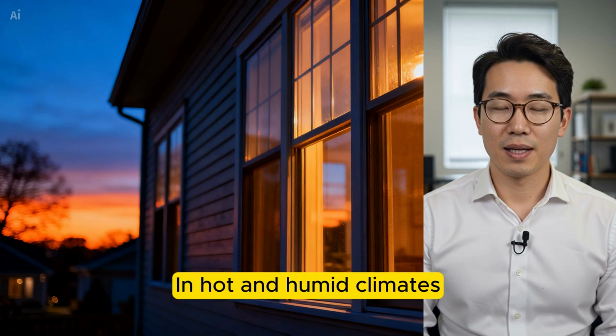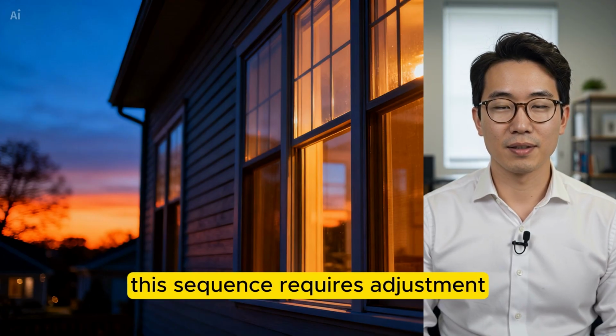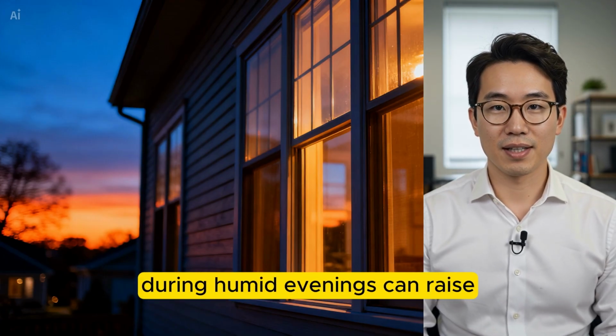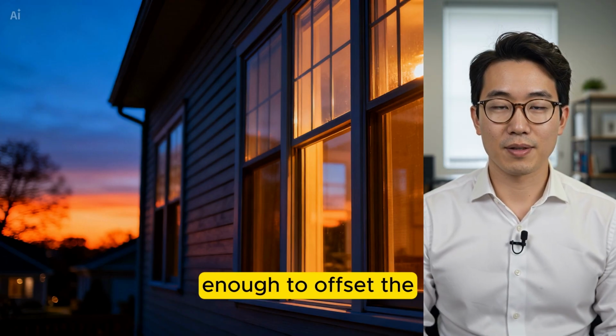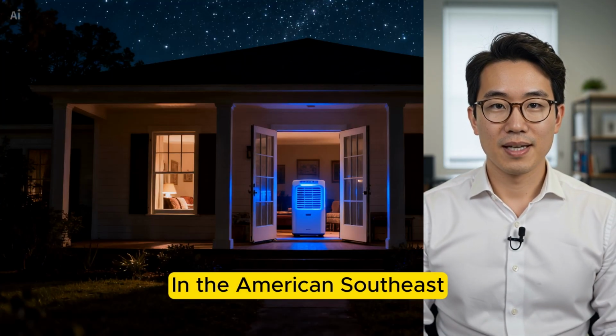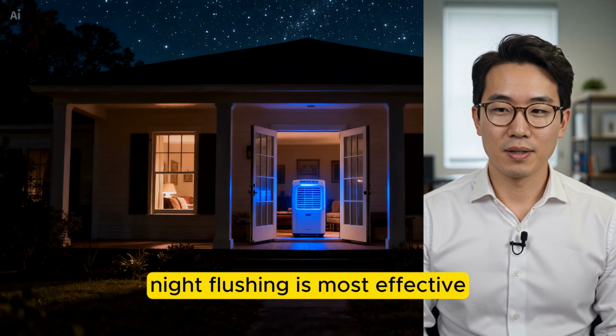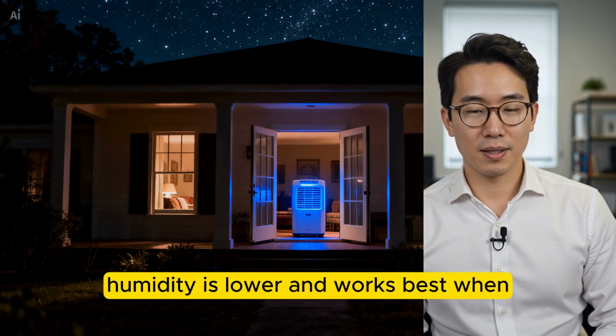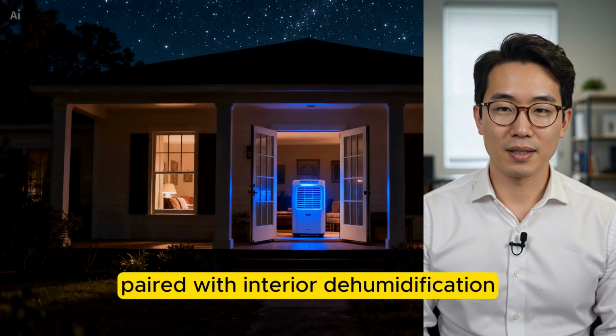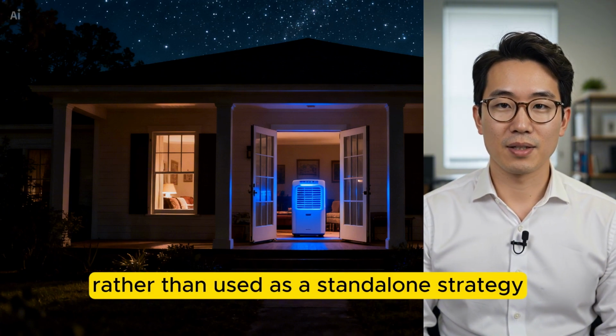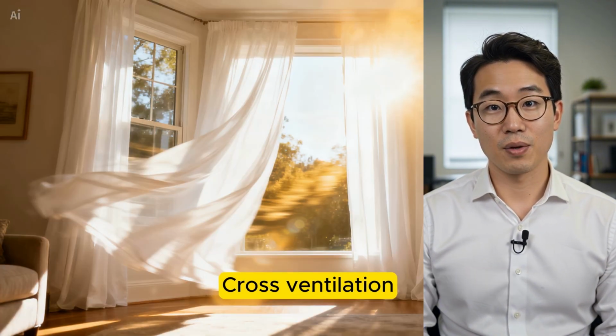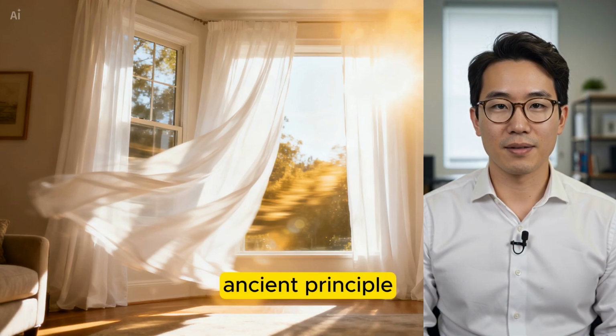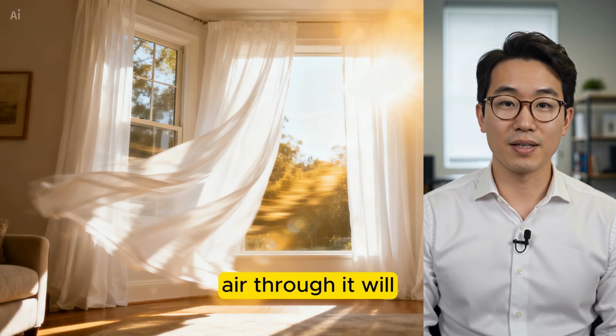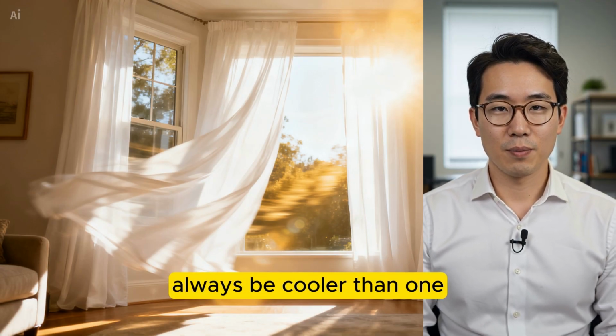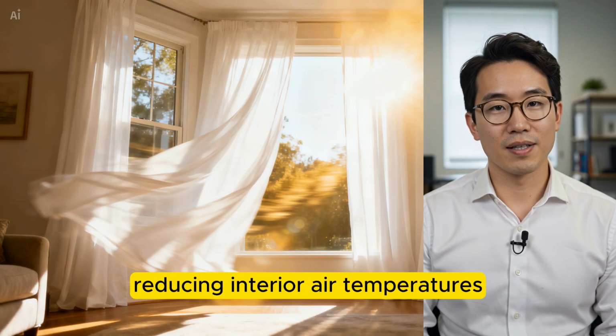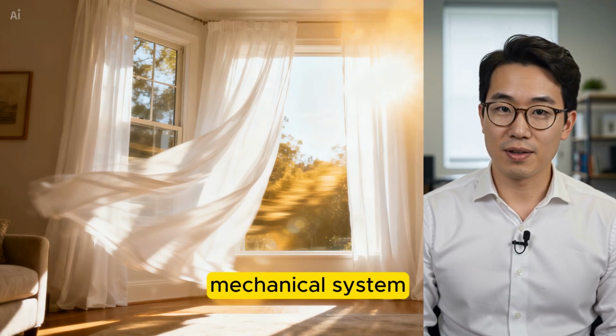In hot and humid climates, this sequence requires adjustment. Outdoor air admitted during humid evenings can raise interior moisture levels enough to offset the temperature benefit. In the American Southeast, night flushing is most effective on evenings when outdoor humidity is lower and works best when paired with interior dehumidification rather than used as a standalone strategy. Cross-ventilation is an approach built on the ancient principle that a building that moves air through it will always be cooler than one that does not, reducing interior air temperatures without turning on a single mechanical system.